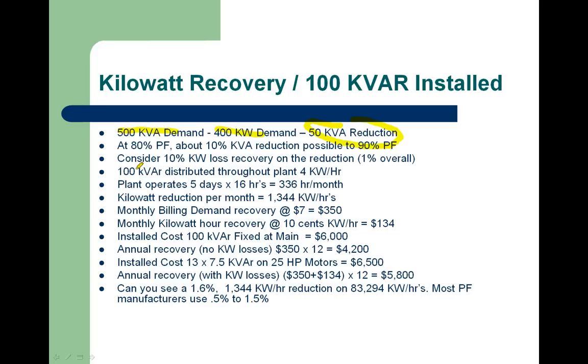So if we look at our 100, we need 100 kVAR over here to be able to reduce our kVA by 50. So if we were to take that 100 kVAR and distribute it throughout the plant, and we're talking about putting it on motors that are at least 250 feet away from the main switchboard or the main meter, we could look at possibly 4 kilowatts per hour recovery.